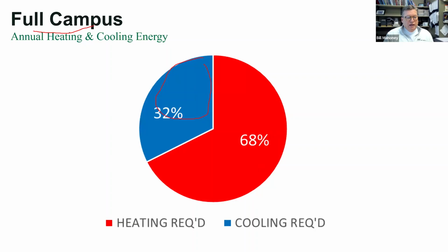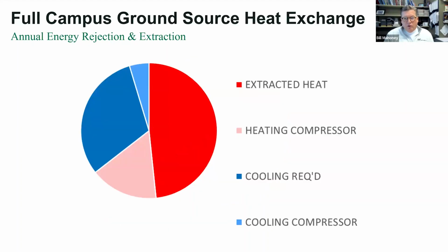Next slide shows you that if we looked at the overall campus where you get some big labs, a lot more cooling spaces, most of the places are air conditioned outside of the buildings we were looking at, it's closer to a 2-to-1 ratio. So 1/3 is the cooling annual energy, and 2/3 of the heat makes it up. And then the next slide tells us that when we get to the overall campus, which ultimately they want to expand the whole system to serve, it's really not that bad where we have to have a complete 50-50 pairing. Because if you think of what's happening in the summertime, I've got a building load here.